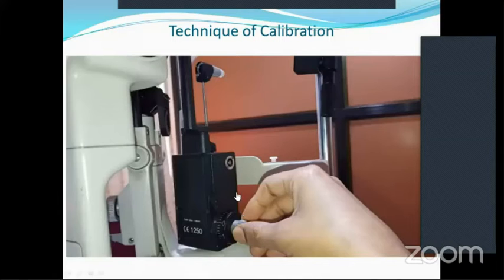This is another video, but I think the video is not going to run. So in a similar way, we measure the errors at 0 millimeters mercury level by simply rotating the knob forward and backward without using the measuring drum. This is a very, very simple technique and it should be used in OPD daily.